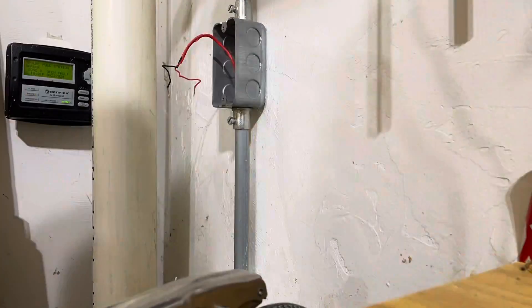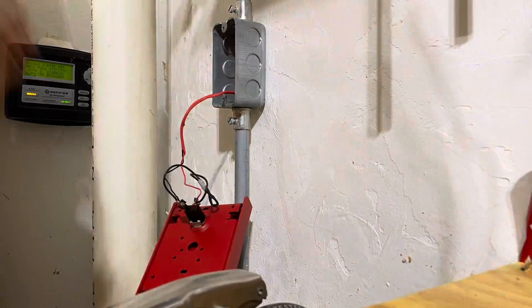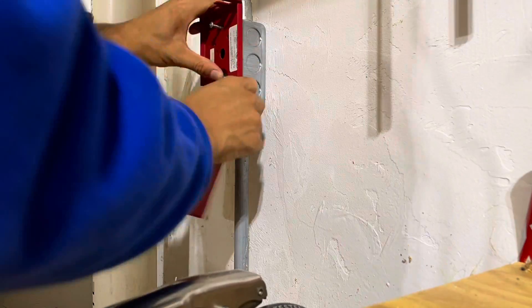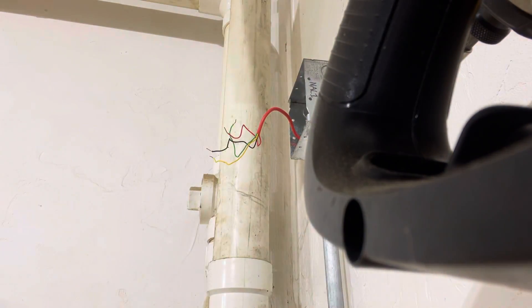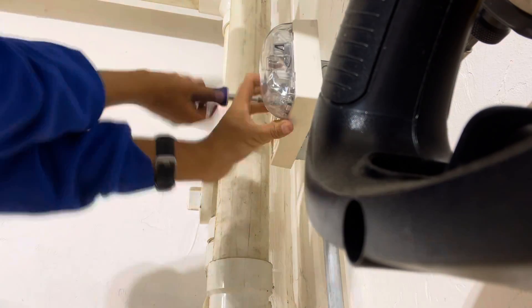Out here in the garage I'm replacing this other federal signal pull station with a conventional simplex t-bar. Nice and standard single action version and up at the horn strobe I'm actually reusing that 4x4 box to install the speaker strobe. In this case because this device is the last device on the circuit it is not that cramped in the junction box and I was able to fit the entire device onto the 4x4 box.